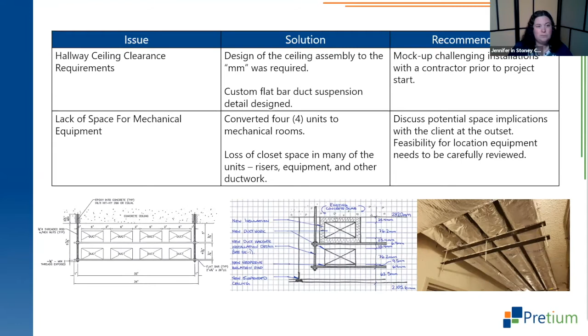I mentioned that we took away some closets for running risers. That created a pretty interesting challenge for us. To create those risers, we had to core through the existing floor slabs, and one of the things we ran into was a lot of embedded conduits. We had done our due diligence as best we could at the outset of this project. The first image shows markings set up on the floor based on a scan we had done of the slab trying to locate embedded conduits. Even at units where the scan seemed to show no conduits anywhere near where we were cutting, we'd start cutting and hit conduits. Less than 10% of the scan results were actually accurate for us.